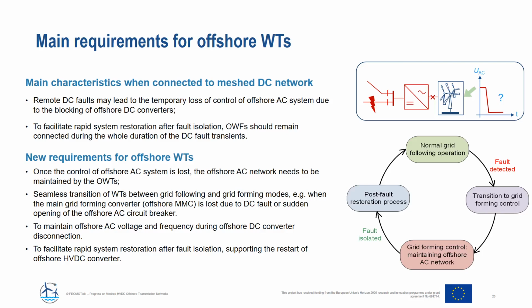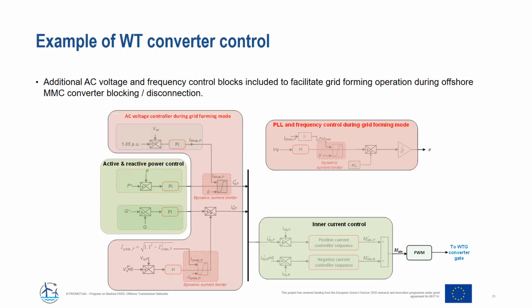Seamless transition of wind turbines between grid following and grid forming modes is required in order to maintain offshore AC voltage and frequency during offshore DC converter disconnection, and to facilitate rapid system restoration after fault isolation, supporting the start of the offshore HVDC converters. This shows an example of the control diagrams for wind turbines.